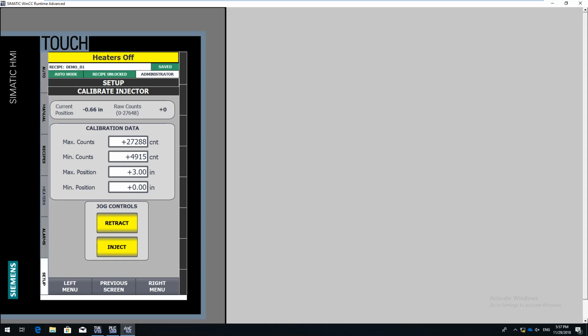Same thing as I would drive the injector all the way up, which again, we only have a 3-inch stroke on most of our injectors. So at 3 inches, what is the value I'm reading there? In this case, I read 27,288. I type those two numbers in, and the system automatically scales for that stroke, and that's all you need to do. So I just need 2 positions in the travel of the injector and document that here, and then it'll scale everything for me.